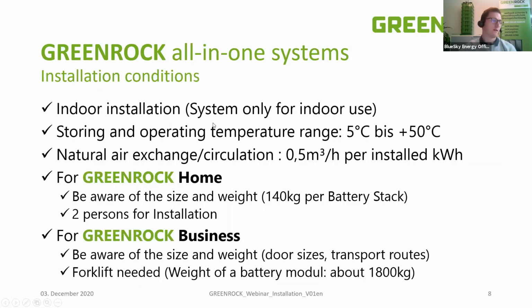Some more information about the conditions: please always install the GreenRock inside, it's really only an indoor use system. Storage and operating temperature ranges from about 5 to plus 50 degrees, though it's not the best case for the system to be at these maximum or minimum values. The best temperature for the battery is around 20 to 25 degrees, where the whole system and the battery stack itself show their best performance and capacity.